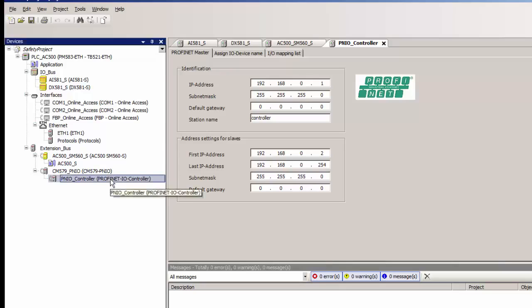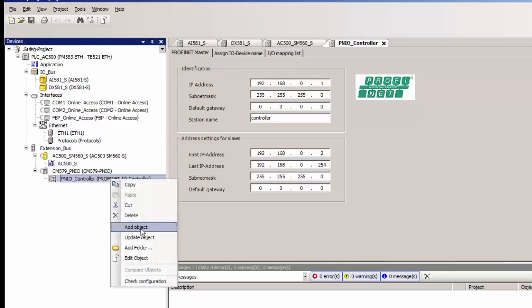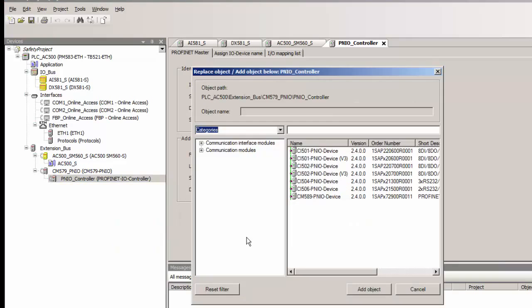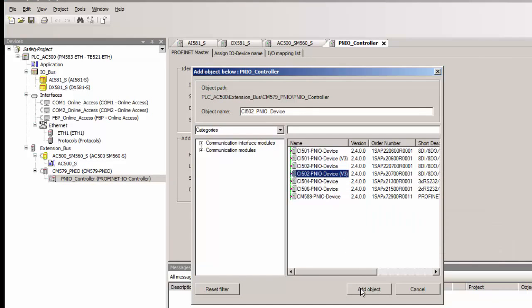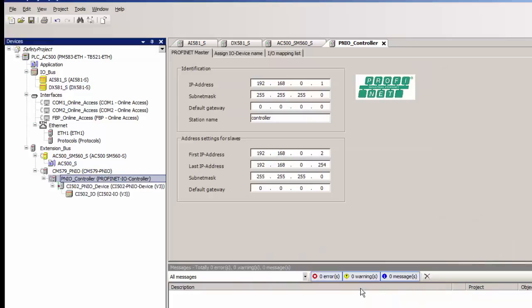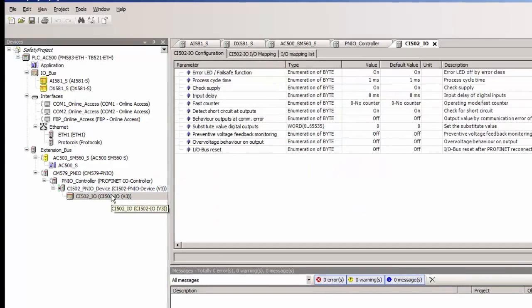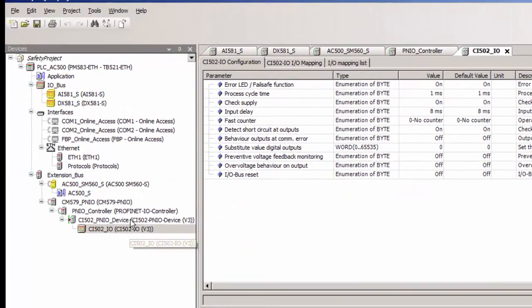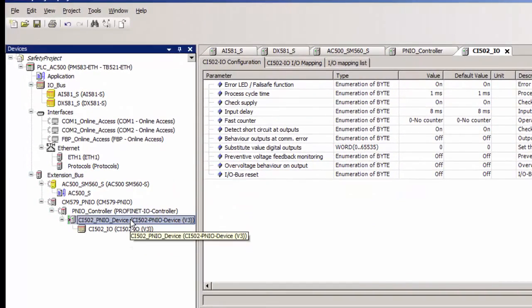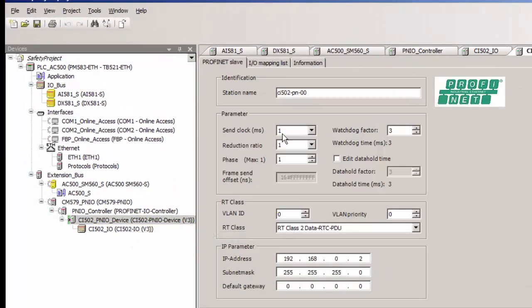Now we add the Profinet IO device module CI502 version 3, which is capable of handling Profinet Safe communication over Profinet Fieldbus. The easy and efficient way to set the station name for this device is just change the last two digits, as per the rotary switch setting on the module.